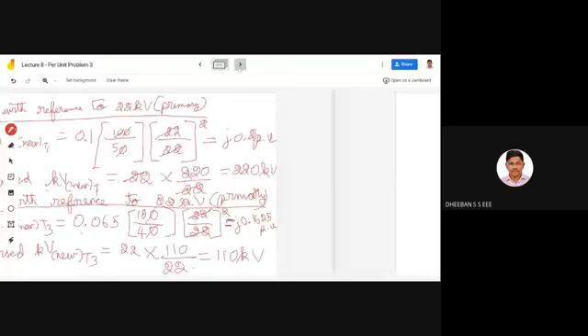0.15 per unit. Okay, and now with respect to T2, here you can see we are again making a jump from the primary to secondary. So if you are making a jump, as I said, you have to revise your kV. So now what happens?